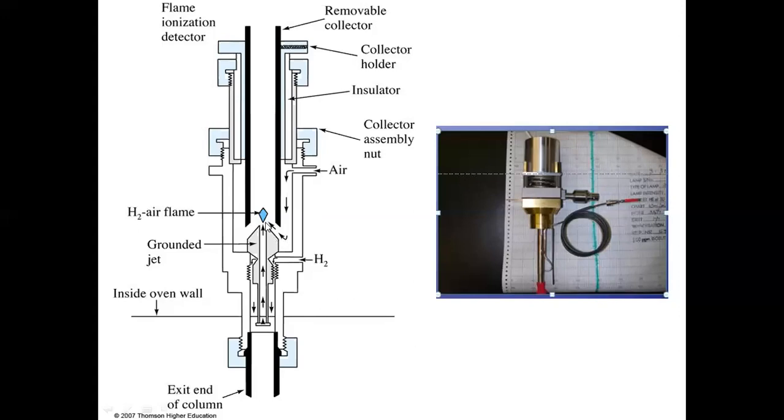Because of the combustion, the ions are going to be formed. Positively charged species are going to be attracted by the cathode, which is negatively charged, or they are going to be repelled by the repeller, the positively charged electrode, which is going to be the anode. At the same time, there is a movement of the electrons also, because of the combustion, electrons are also generated because the compounds are hydrocarbons. As a result of the attraction or repulsion of these positively charged species by the cathode or the anode, a movement of electrons is expected. As a result, there is a generation of current.